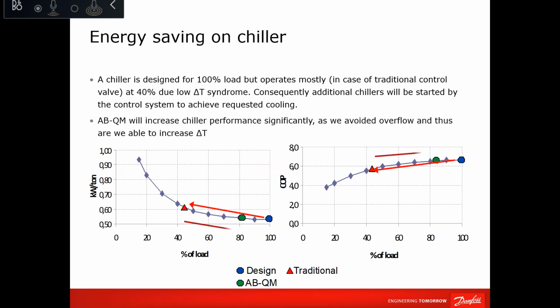Chiller. Here it's showing that if we have multiple chillers on a common header, it consumes less energy if you have one chiller running at 100% rather than two chillers, each of them running at 50%, because of the starting current, because of the design parameter of the chiller, which will be changed if you have overflows in your system.